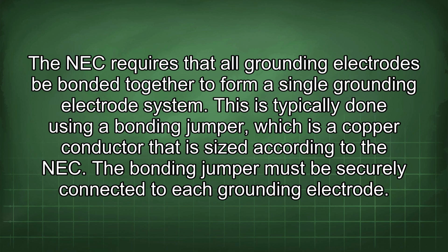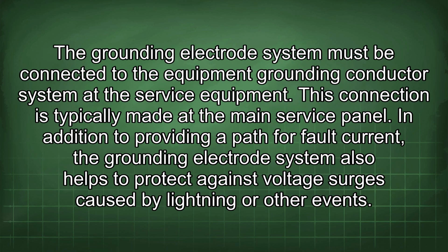This is typically done using a bonding jumper, which is a copper conductor that is sized according to the NEC. The bonding jumper must be securely connected to each grounding electrode. The grounding electrode system must be connected to the equipment grounding conductor system at the service equipment. This connection is typically made at the main service panel.